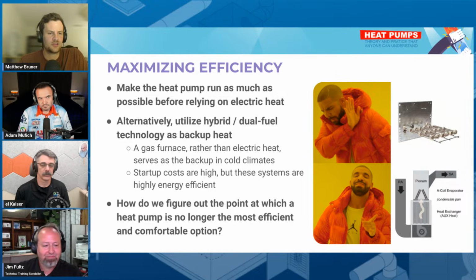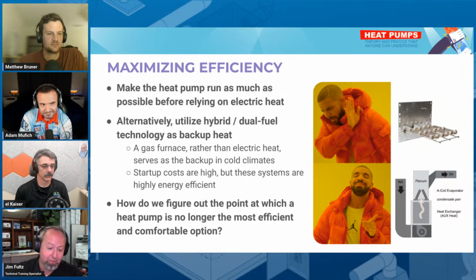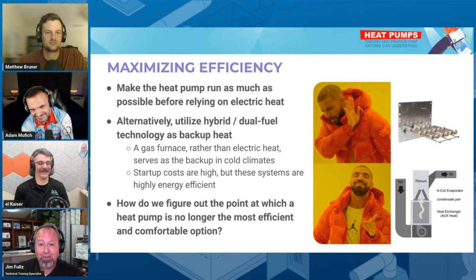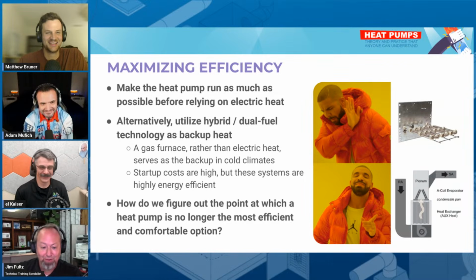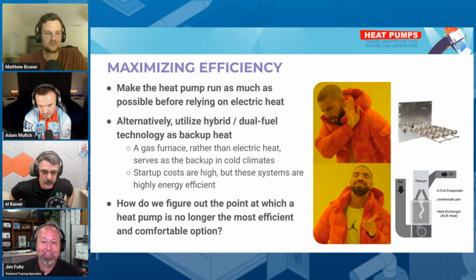Okay. Any other closing comments? Well, yeah, I could open up a big can of worms right now from this slide, because personal preference and more than that is, if you're putting a dual fuel and a second stage gas furnace in with a heat pump, you want that coil before the furnace, not after, because if you do it according to this picture here and you're cycling that furnace on, as we've talked about cycling the electric resistance heat on, you're going to put so much heat on that coil that you're going to trip the limit. Or if it's an inverter, you're going to cause it to go crazy.